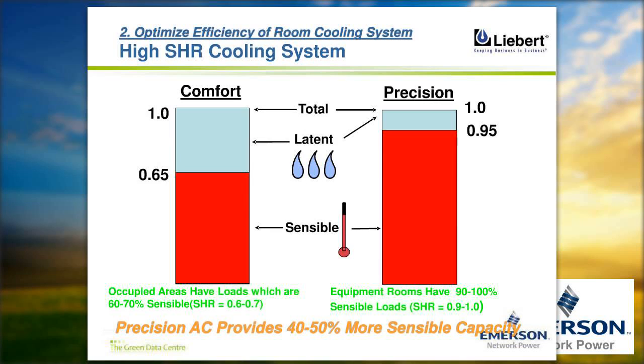In India, many data centers are still using normal comfort air conditioners, especially small server rooms. We are seeing people using split ACs, window ACs, and some VRV systems. But precision ACs are recommended because they have a high sensible heat ratio and take care of the data center, and the design duty cycle is also very high, considering 24/7 operations. This is one strong recommendation, because the consumption of a comfort AC is relatively higher compared to a precision AC in the long run, and the life cycle cost of a comfort AC is also very high. So usage of precision AC is very critical here.